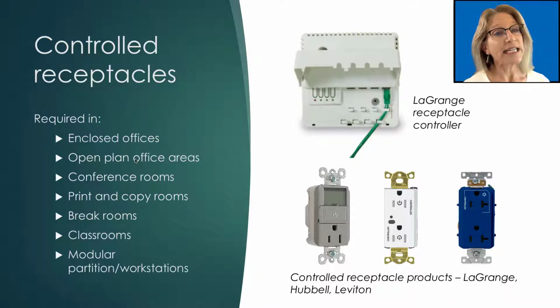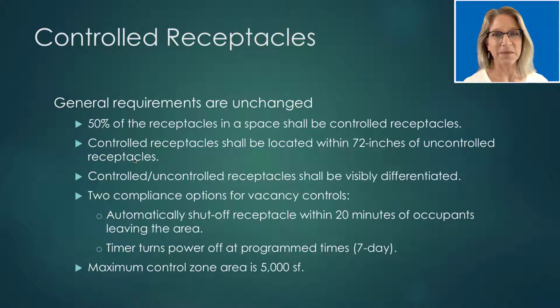These controls are required in enclosed offices, open plan office areas, conference rooms, print and copy rooms, break rooms, classrooms, and within modular partition or workstations, so those cubicles that can be reconfigured and moved around within the space. The general requirements under this provision haven't changed. They require that 50% of the receptacles within the space need to be controlled receptacles. And a controlled receptacle has to be located within 72 inches of an uncontrolled receptacle. And then the two different types of receptacles need to be clearly visibly differentiated.